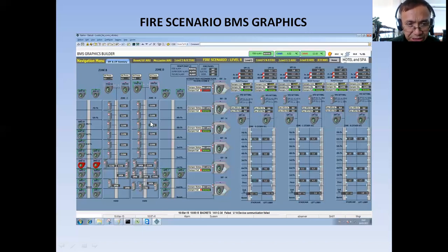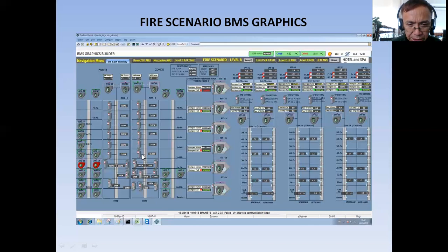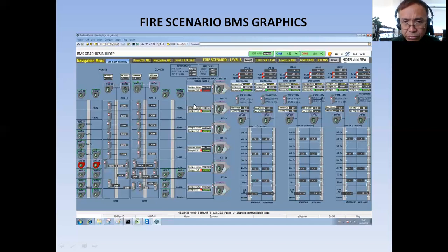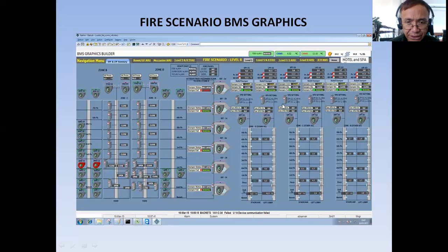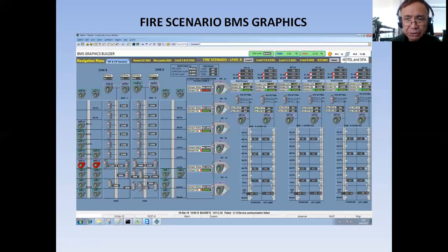Let's say there is fire on this level — third floor. This motorized smoke fire damper will open so that fresh air will be introduced there and the smoke will be pushed going to the dome where the smoke extraction fans are working, so the smoke will be vented out of the building. When there is fire, you will see only the equipment that are working in the event of fire. I'm giving the BMS operator a chance to see what's going on when there is a fire scenario in the building.